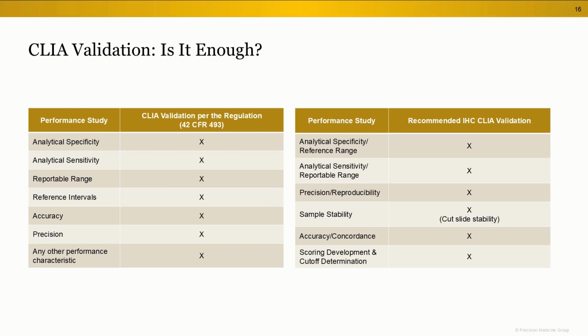We utilize concordance and method comparison studies to satisfy accuracy requirements, because the term accuracy is really more appropriately applied when there's a reference standard used, and that just doesn't exist in the technology of IHC. There aren't any calibrators for our instruments. So additionally, we conduct sample stability studies like you were talking about, Kennon. Those can include reagent stabilities or cut slide stabilities, as well as provide scoring development and cutoff determinations to support both a robust test system development and the necessary information for your regulatory submissions.